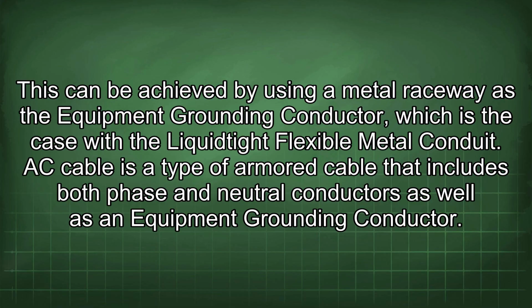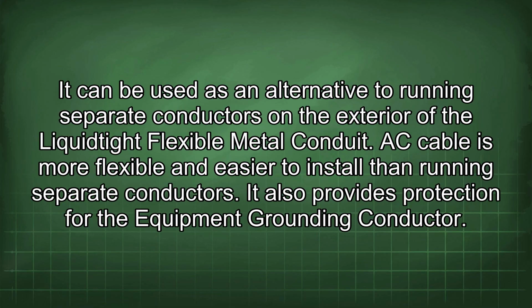AC cable is a type of armored cable that includes both phase and neutral conductors as well as an equipment grounding conductor. It can be used as an alternative to running separate conductors on the exterior of the Liquidtight Flexible Metal Conduit. AC cable is more flexible and easier to install than running separate conductors. It also provides protection for the equipment grounding conductor.